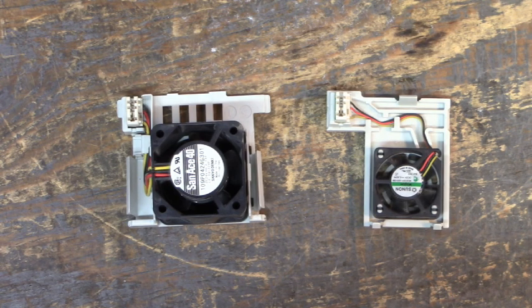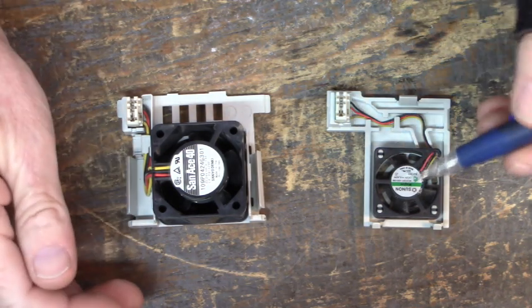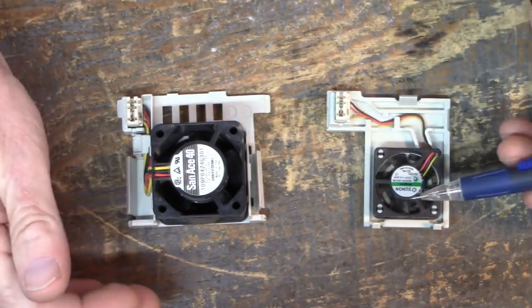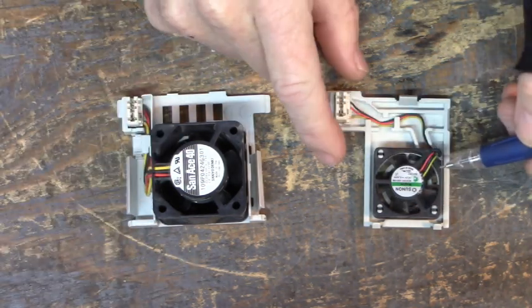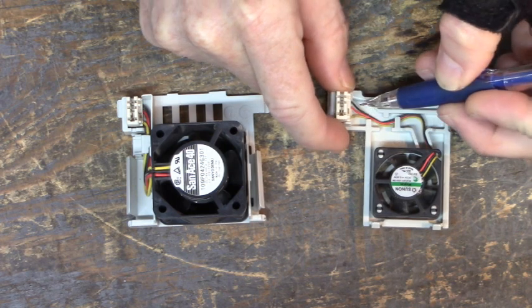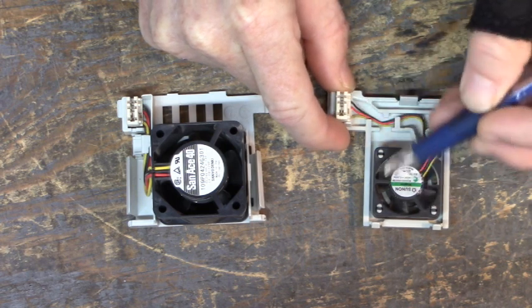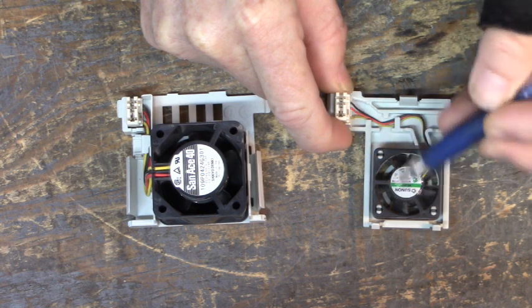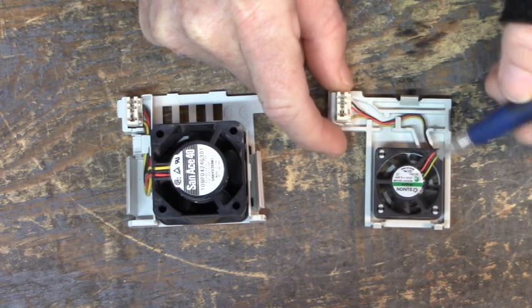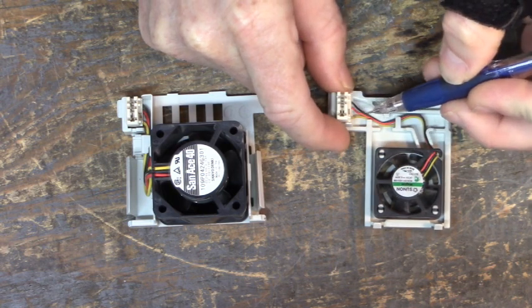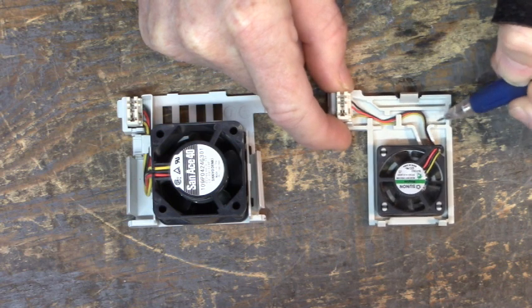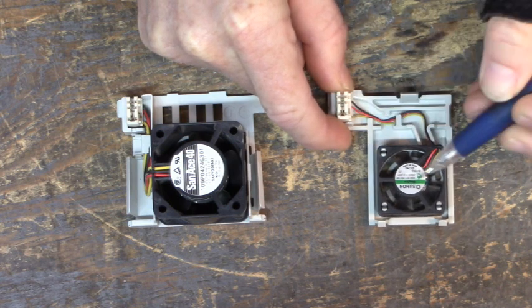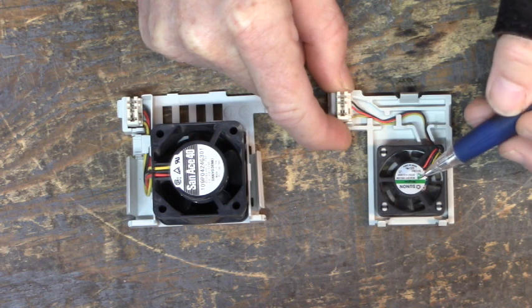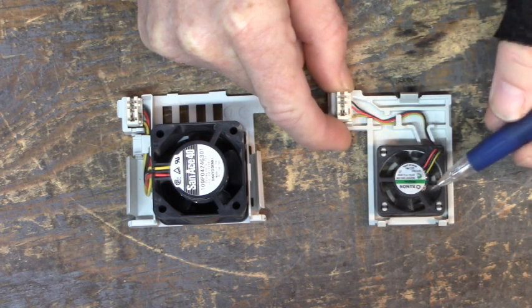Now you're probably wondering, how does the drive know that the fan's not working? Well, here we have a red wire and a black wire that power up the cooling fan to start spinning. But there's another wire, a yellow wire, and that is an output to the drive that tells the drive that the cooling fan is spinning.